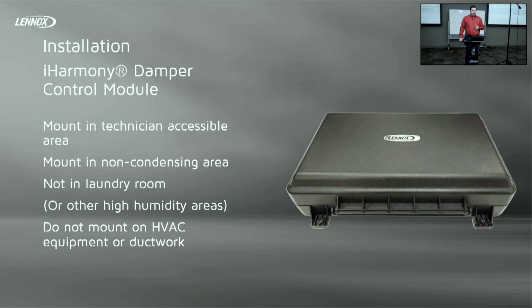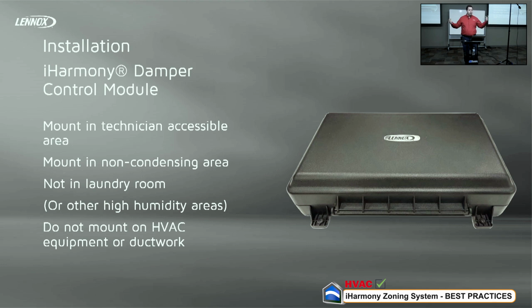So with the damper control panel, again, you want it someplace that it can be accessed and you can run all your wires back to, because all your dampers and your zone stats are going to be wired back to it. Usually it's close by your air handler or furnace, by your indoor unit. You don't want it in some area where there's going to be a lot of humidity. It's got its own protective case, but you're still going to get some infiltration. So if you're in an area that has poor ventilation and high humidity, an easy example being a laundry room, that's probably not going to be common for a lot of the installations you're going to see, but it's something to keep in mind if you run across one of those situations. Occasionally these get installed in a commercial application, and you'll see those types of issues.